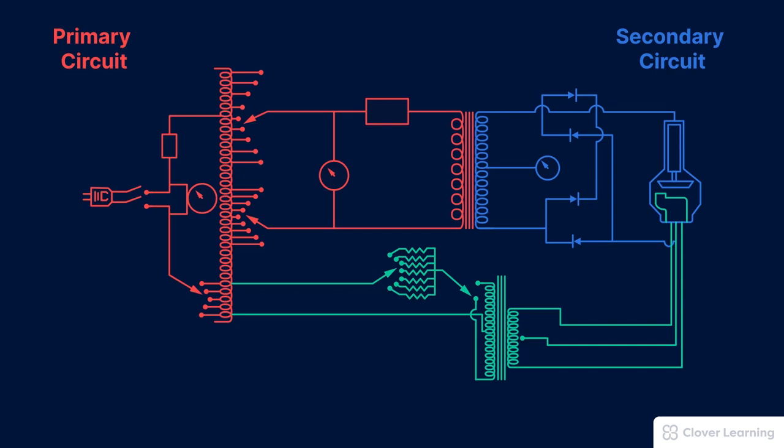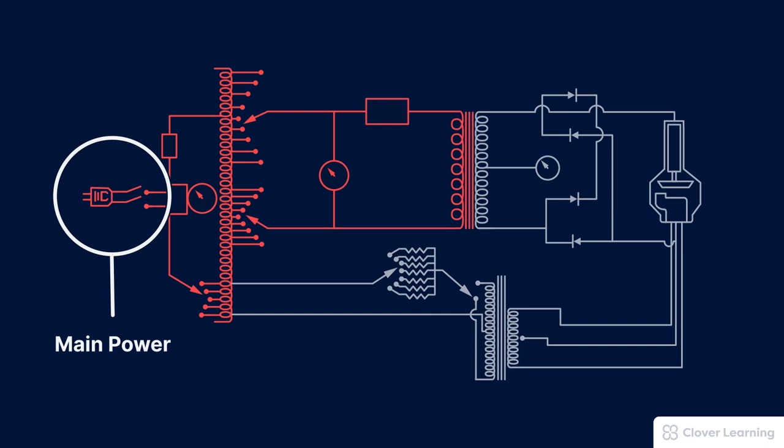Each of these circuits supports the process of x-ray production in different ways, and this lesson is about the primary circuit. We call this the primary circuit because this is where the main power supply comes into the x-ray machine. Another reason we call this the primary circuit is because it's on the primary side of the step-up transformer.